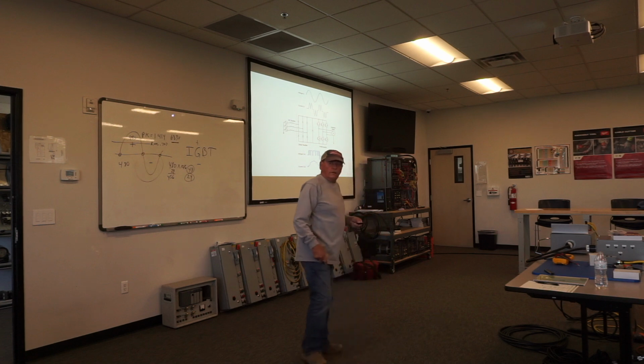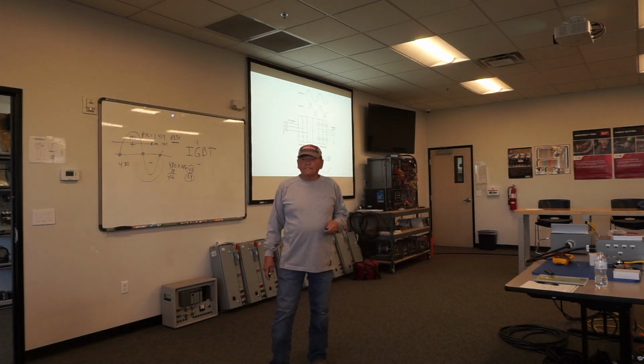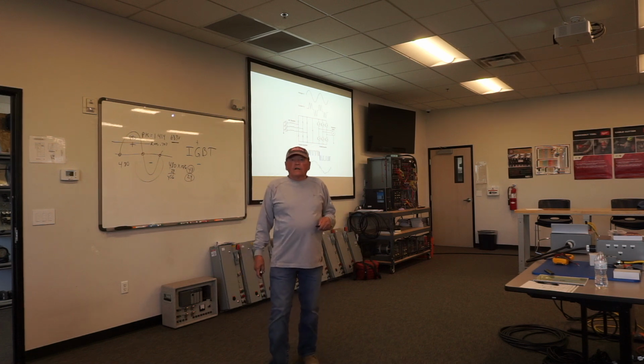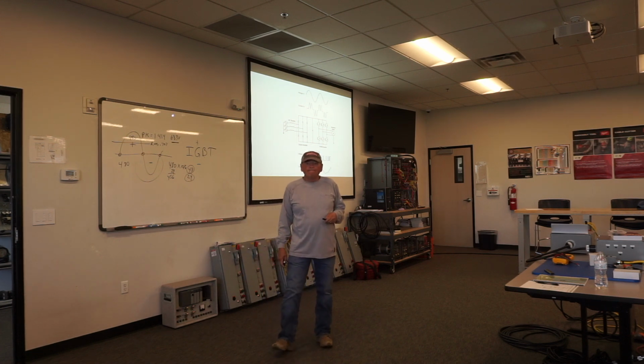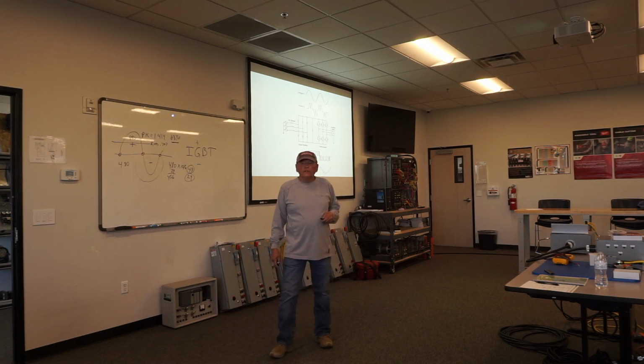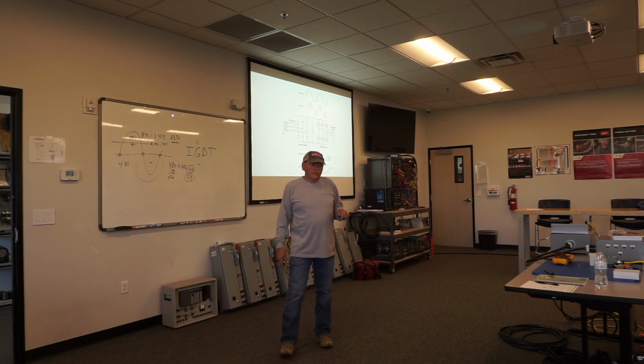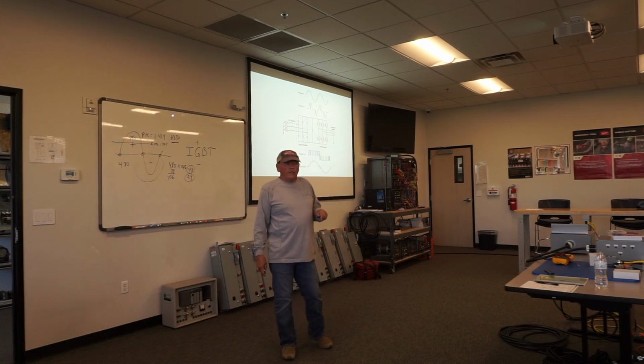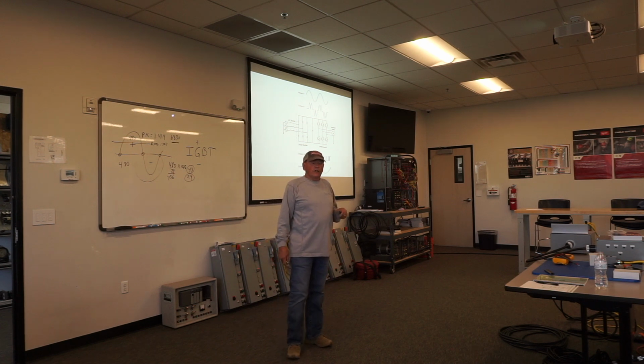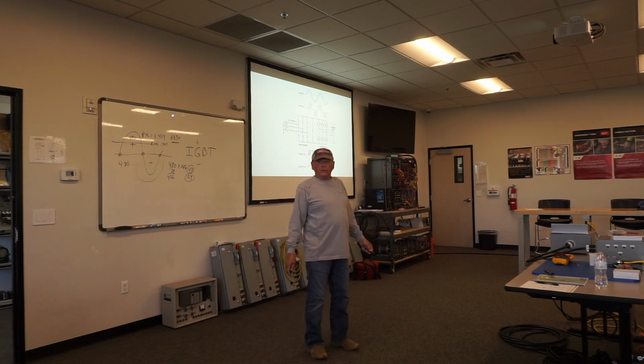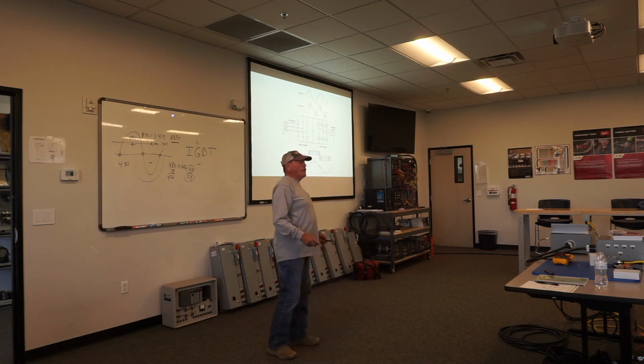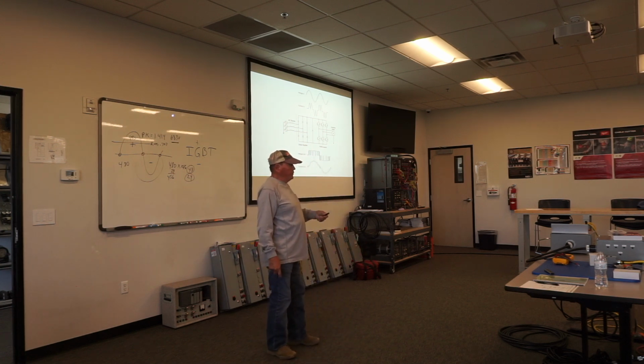So I got a question, Carl. What would cause a voltage sag that would last long enough to affect that drive? Because we've all turned on a motor and seen the lights dim just a little bit, but they just dim and come right back. Is that long enough? Good question, because it all depends on the drive manufacturer. What is it capable of riding through? So it's the ride-through capability of the end-use device.